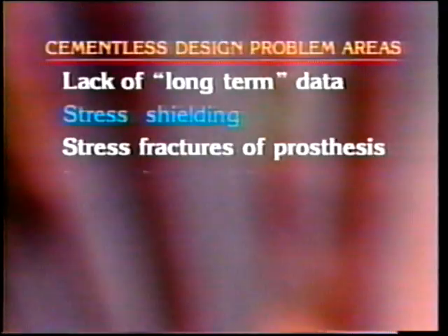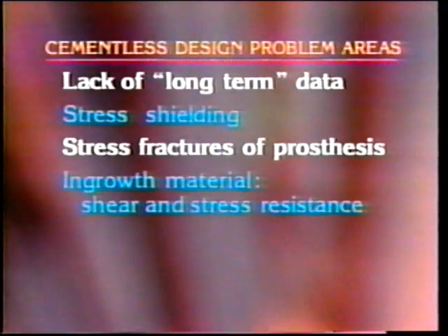The ingrowth material, how will it resist shear and stress? That too is a problem. Not only do we have to worry about bone growing into the pores, but also one has to worry about shear fractures of the porous material from the substrate metal. This can certainly become a problem with loosening as a result.